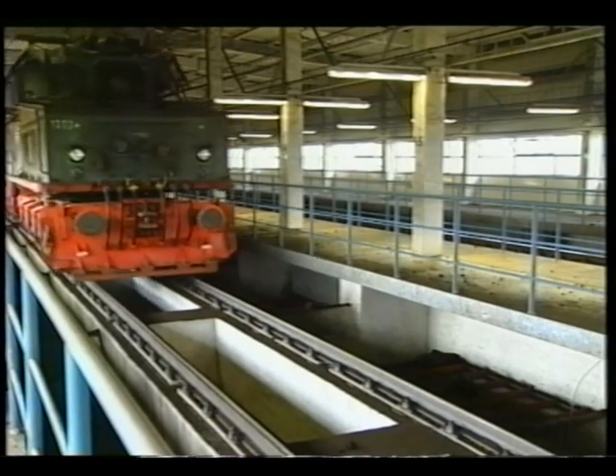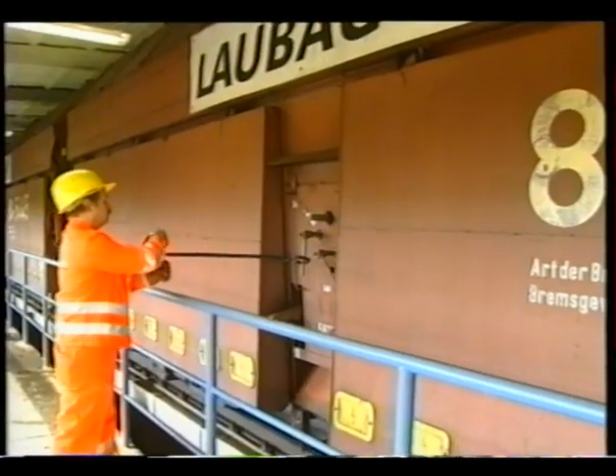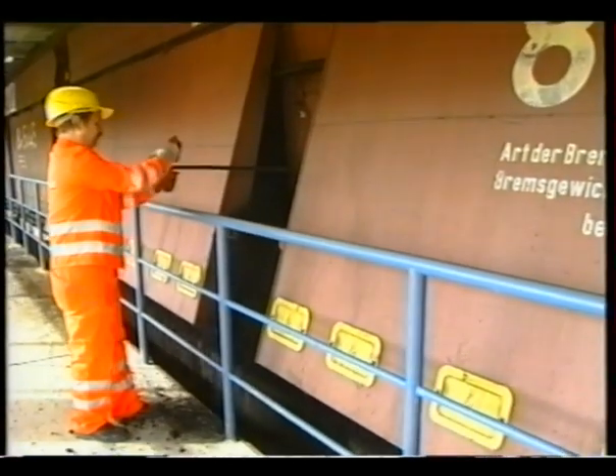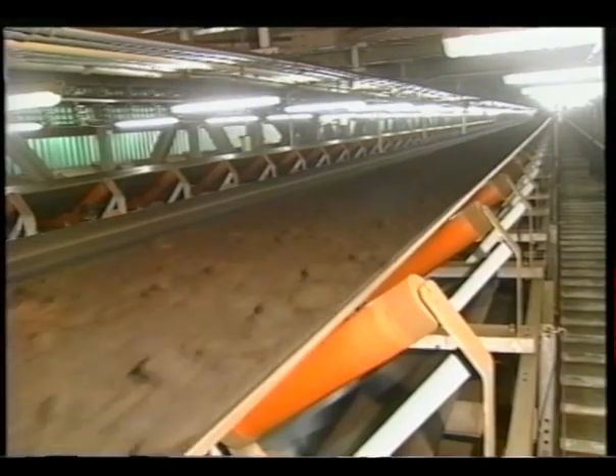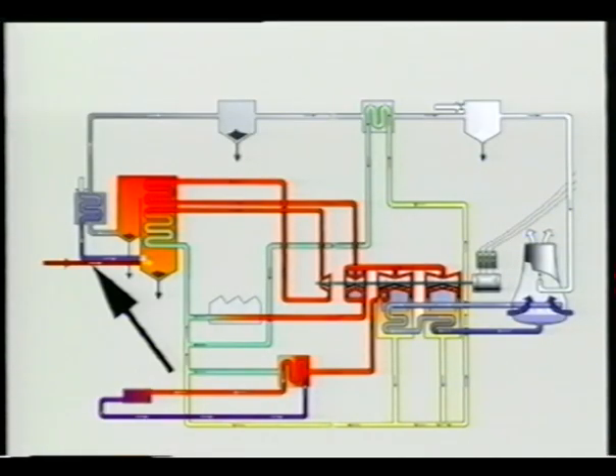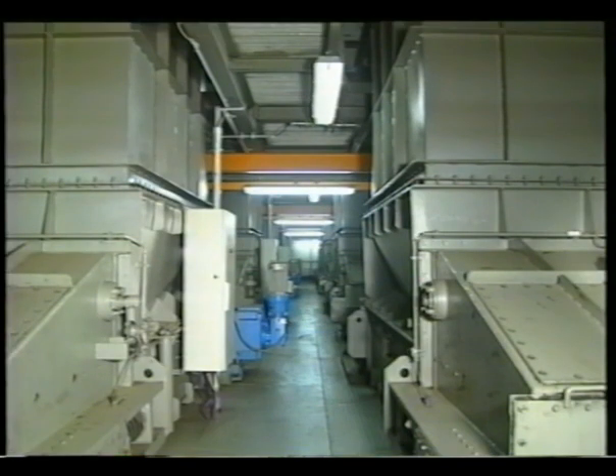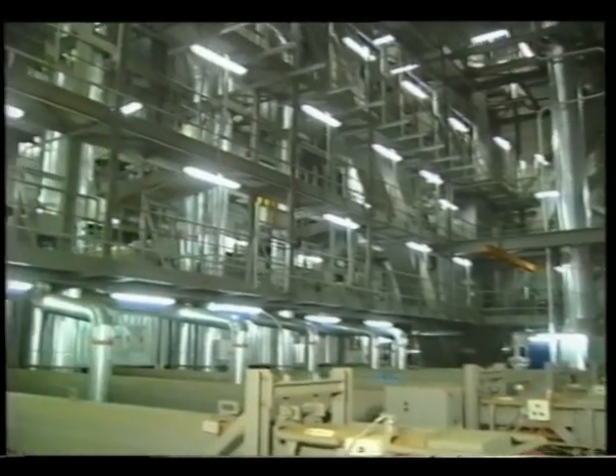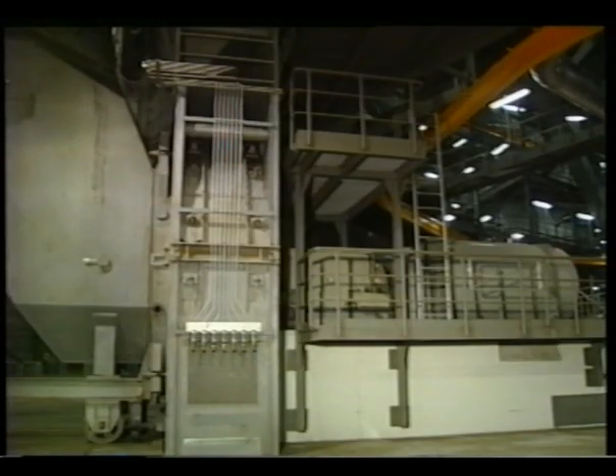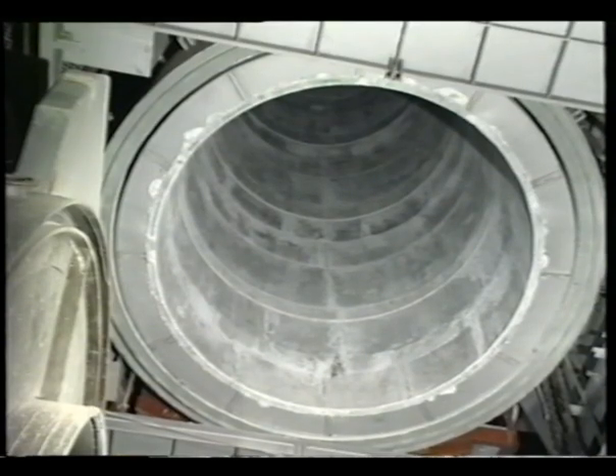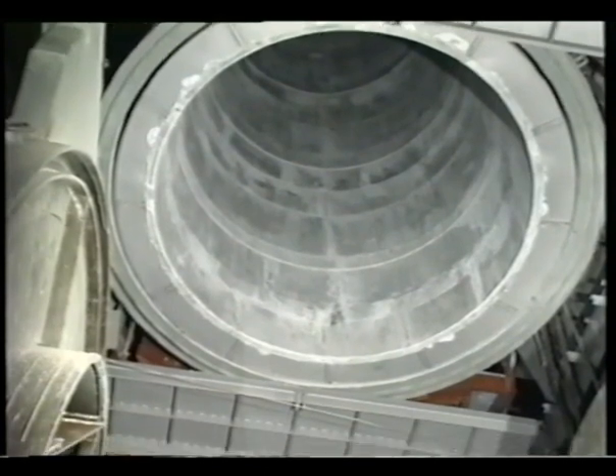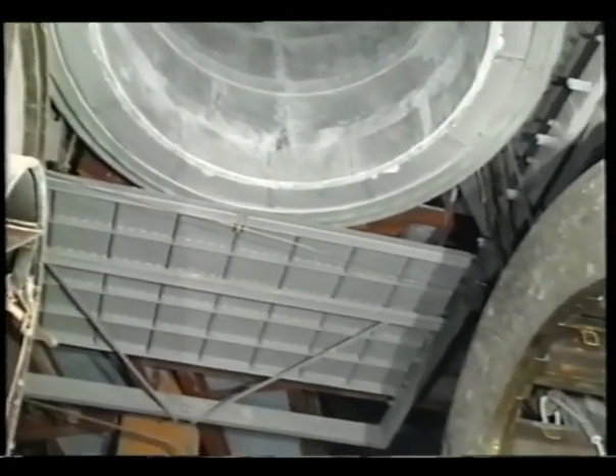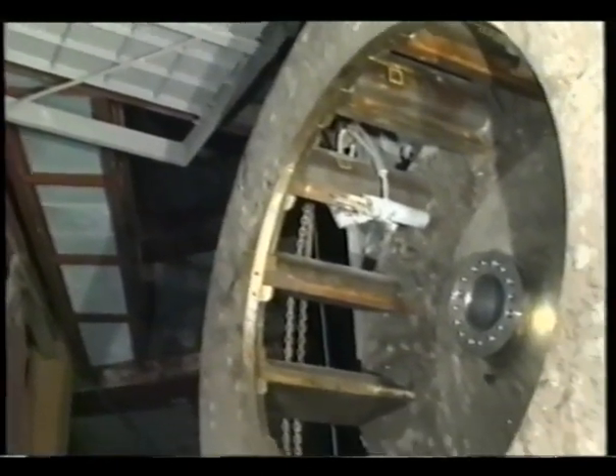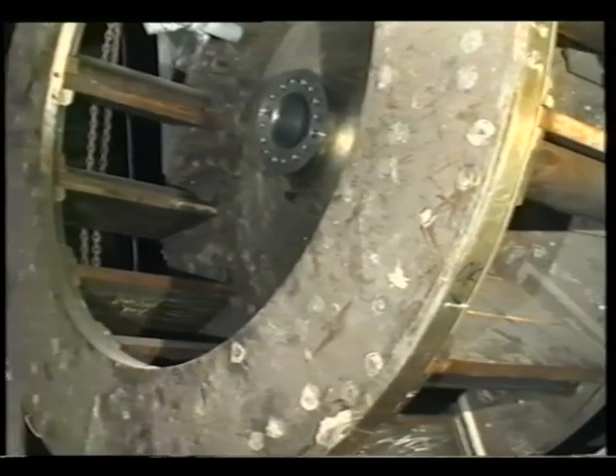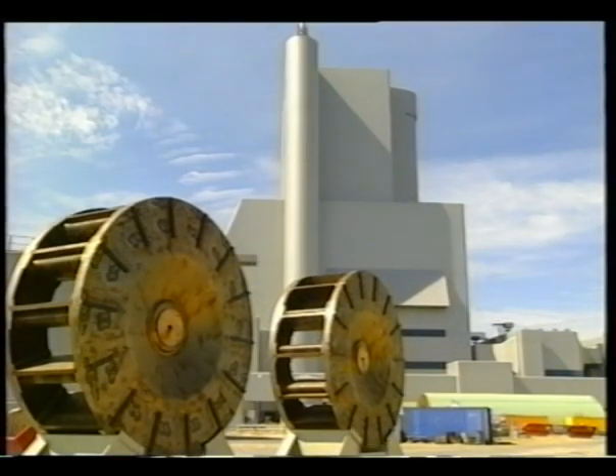Once it has been delivered by the coal mine train, the coal is tipped into the power plant and coarse ground. It goes from the bunker over conveyor belts and down shafts to the coal mills. The raw lignite is ground by the beater mill wheels into coal dust and blown through the burner into the boiler. There are 8 coal mills to each boiler. The beater mill wheels have a diameter of 4 meters and each one processes around 100 tons of fuel per hour.